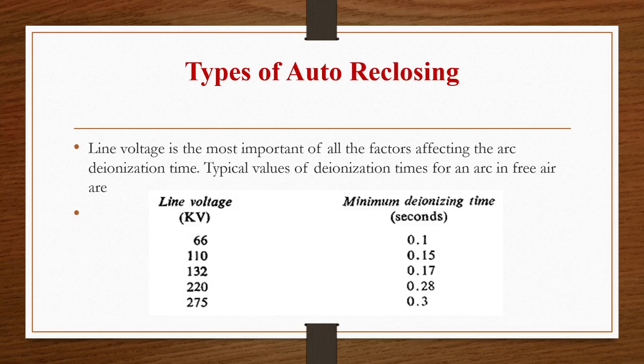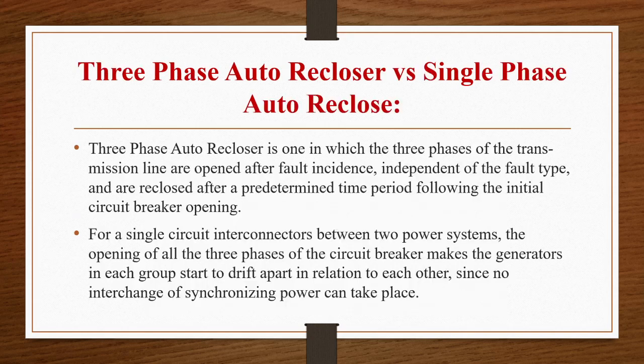Typical values of deionization times for an arc in free air are as follows: line voltage on the left-hand side is given in kilovolts and minimum deionization time in seconds is given on the right-hand side. For 66 kV, the minimum deionization time can be 0.1; for 110, 0.15; for 132, 0.17; for 220 kV line voltage, the deionizing time can be 0.28; for 275 it is 0.3. Now let us see the comparison between three-phase auto reclosure versus single-phase auto reclosure.